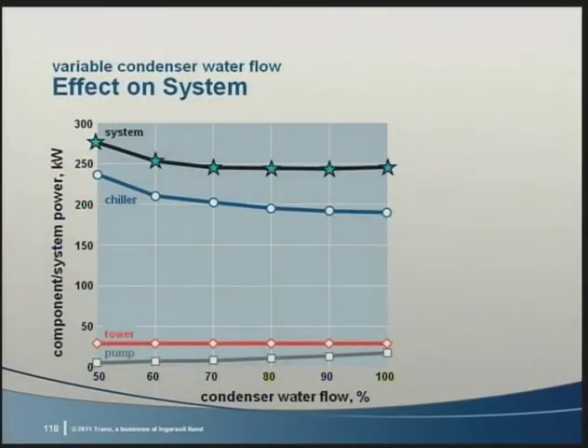Here, we show results assuming the cooling tower fan speed is held constant at 100% to produce the coldest water possible coming back to the chiller. The minimum chiller plus condenser water pump plus cooling tower kW occurs between 80 and 90% of the condenser water flow rate. But it's not that easy. So far, we assume that the cooling tower fans are operating at full speed all the time. Because ASHRAE 90.1 requires speed control on cooling tower fans in many applications, and as we just discussed, there are significant savings by finding the correct tower set point, many people put VFDs on their cooling tower fans and want to use those VFDs. So, we need to examine how the condenser leaving water temperature changes when we decrease the flow rate and tower fan speed.